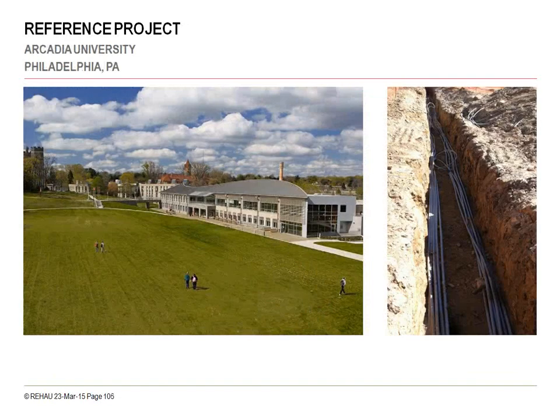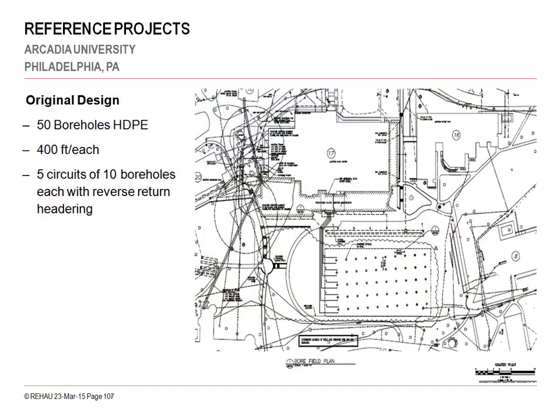I'm just about through. I just wanted to talk for a moment about the Arcadia University project. This was a student center. You can see the quad area there for the students where they also played lacrosse. And this project was originally designed as 50 boreholes of HDPE. The engineer was Benoni out of Philadelphia. Here is the original design. You can see the 50 boreholes. There are 5 circuits of 10 boreholes per circuit. And so you can see the trenching of the 10 boreholes and the reverse return headering, this supply and return off of each trench going down into the building, into the mechanical room.